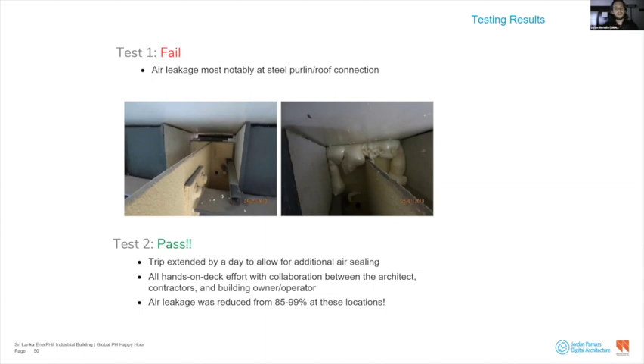As we were walking around the building, we could hear whistling and louder noises every 15 feet or so. We were searching for hours and could not figure out what the heck was wrong. We found some small issues, but we were like, this is not it. Then we looked up at the underside of the roof and said, well, I think we see daylight - is that daylight on the other side of the roof?